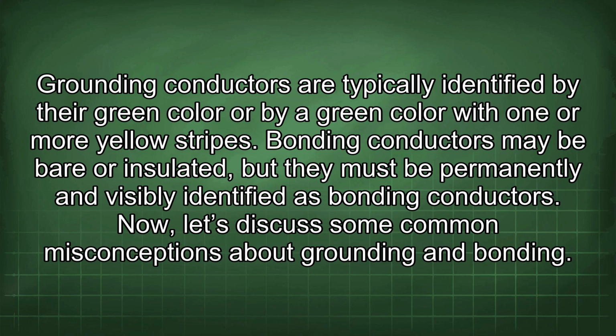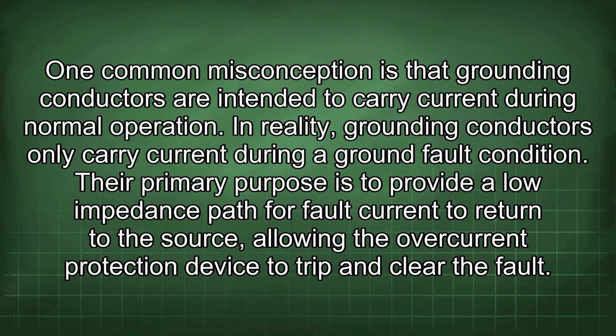Now, let's discuss some common misconceptions about grounding and bonding. One common misconception is that grounding conductors are intended to carry current during normal operation. In reality, grounding conductors only carry current during a ground fault condition. Their primary purpose is to provide a low impedance path for fault current to return to the source, allowing the overcurrent protection device to trip and clear the fault.